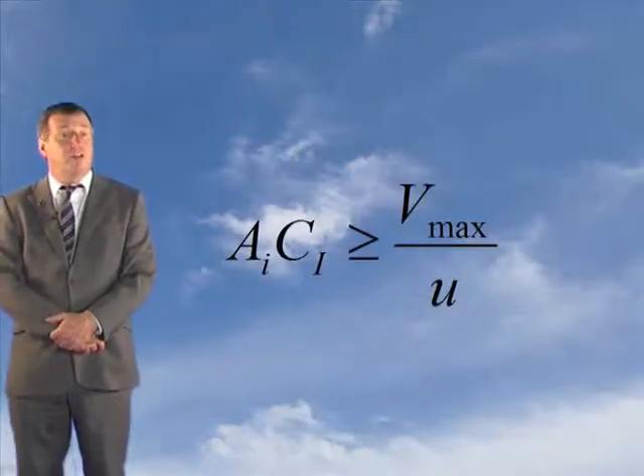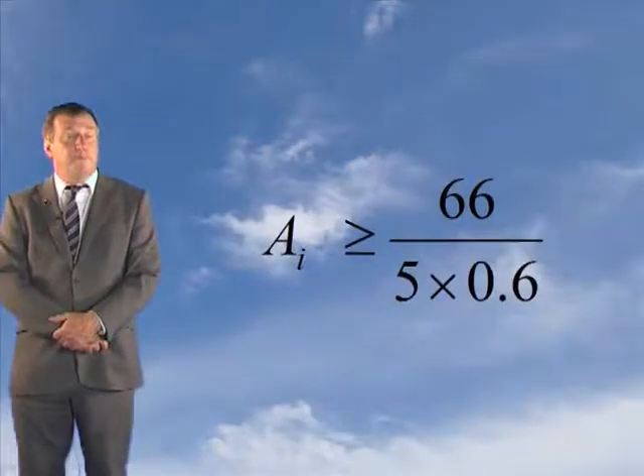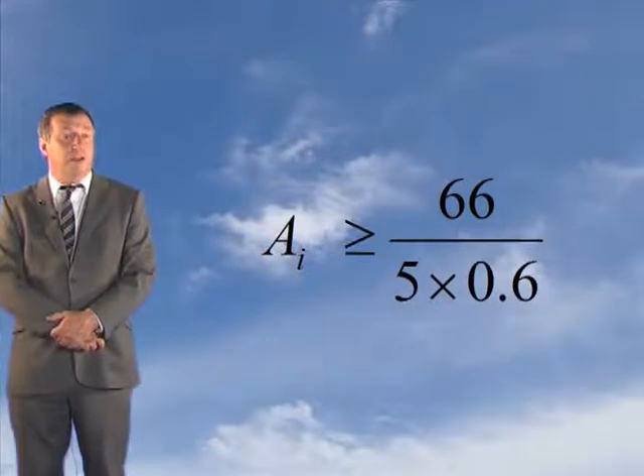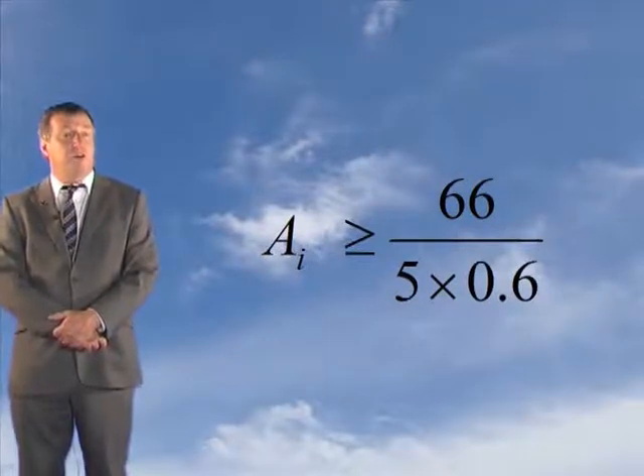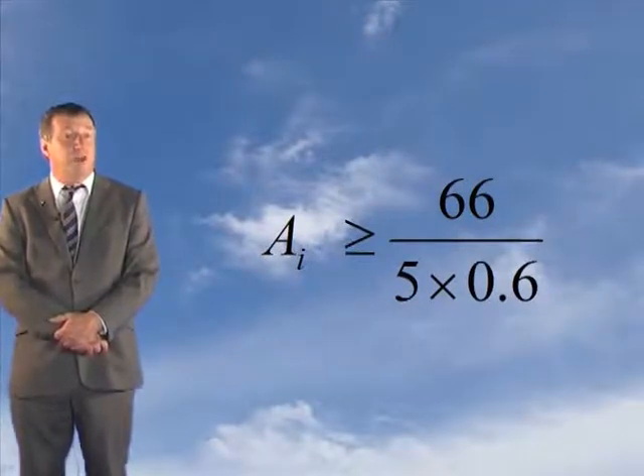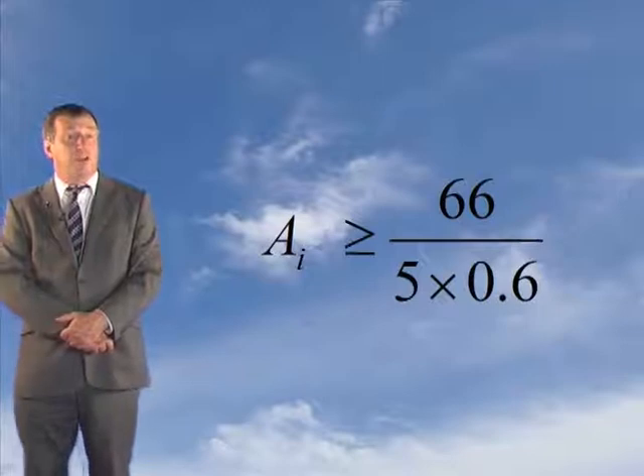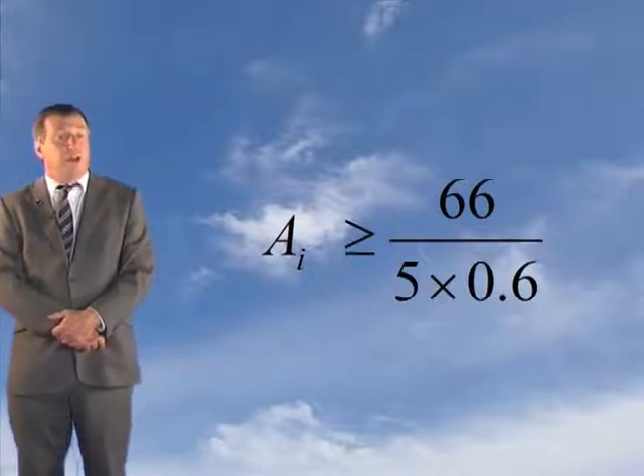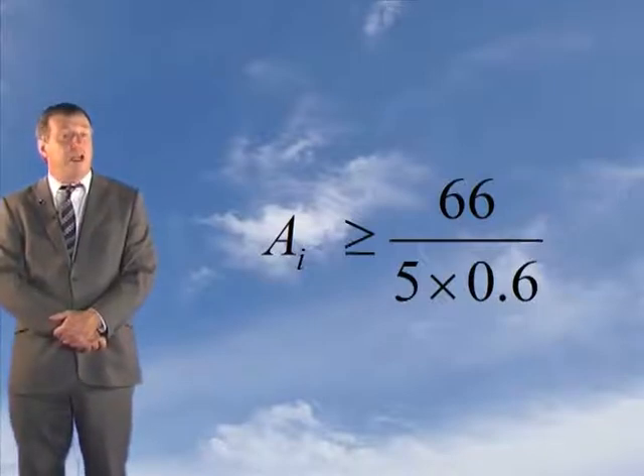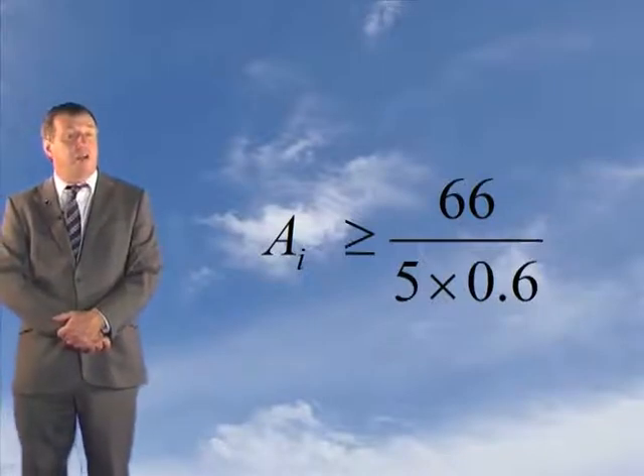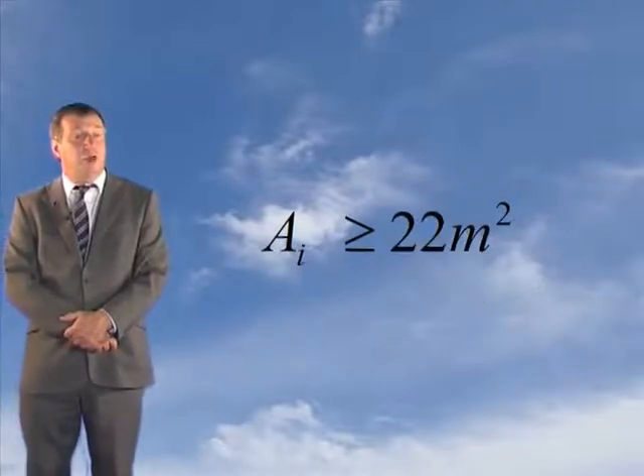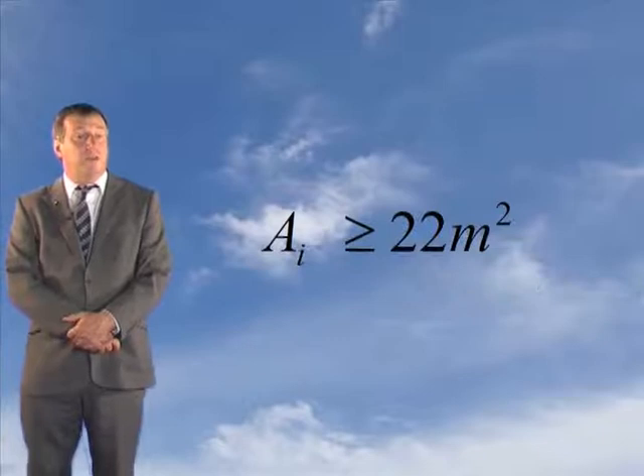Putting our figures into the equation gives us the results shown here. AI must be greater than or equal to 66 divided by 5 multiplied by 0.6, and if we evaluate that, we get AI has to be greater than or equal to 22 square metres.